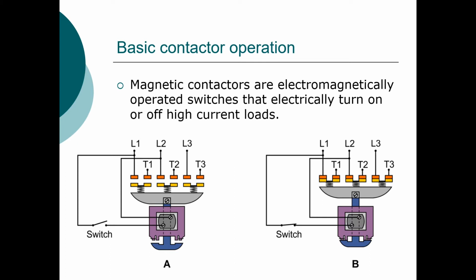A relay or a contactor is an electromagnetic switch meant to turn on and off loads. Magnetic contactors are specifically used for turning on and off high current loads. The contactors are being controlled by remote devices like switches and sensors that we call pilot devices, and they can be push buttons, thermostats, photocells, limit switches, or even float or pressure switches. The pilot devices can either be manual or automatic, and they will energize the coil, which creates the magnetic field that pulls in the armature.